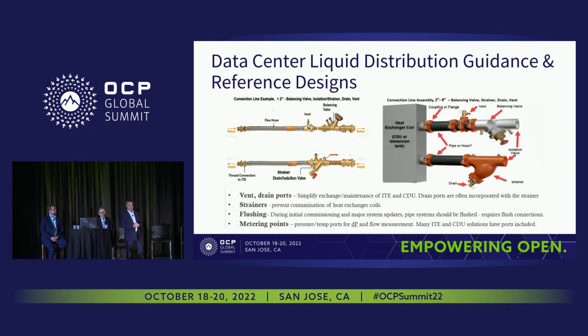Another part that came out of OCP, the liquid distribution guidance and reference designs. Again, this is an excerpt from the white paper and the publication. This is showing some of the valve train for the recommended connection methodologies for the ACS solutions to the FWS. So we've got balancing valves, vents, drains, strainers, and so on - all those things that we know need to go into these connections.